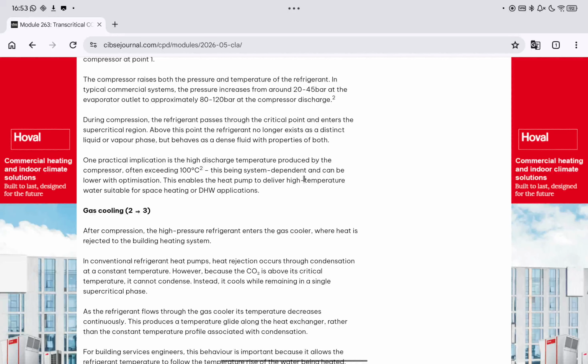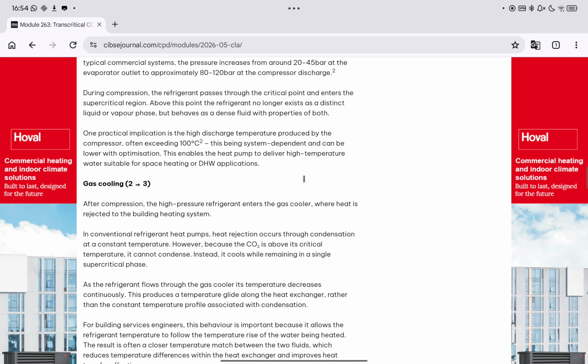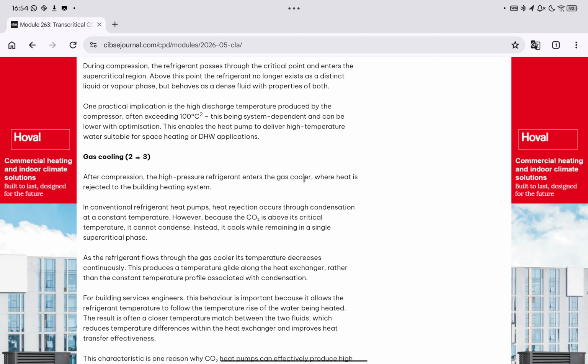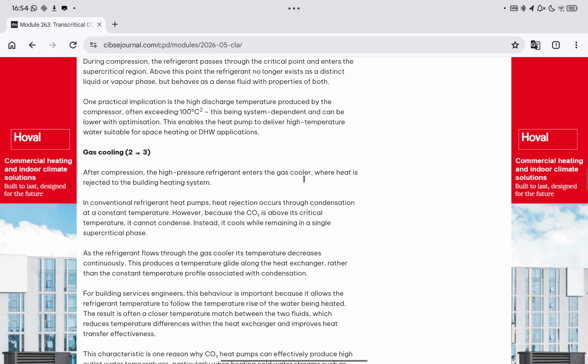Gas cooling. After compression, the high pressure refrigerant enters the gas cooler, where heat is rejected to the building heating system. In conventional refrigerant heat pumps, heat rejection occurs through condensation at a constant temperature. However, because the CO2 is above its critical temperature, it cannot condense. Instead, it cools while remaining in a single supercritical phase. As the refrigerant flows through the gas cooler, its temperature decreases continuously. This produces a temperature glide along the heat exchanger rather than the constant temperature profile associated with condensation.